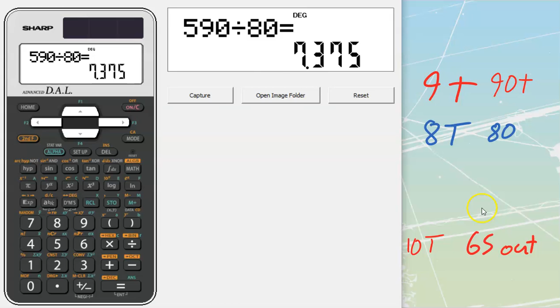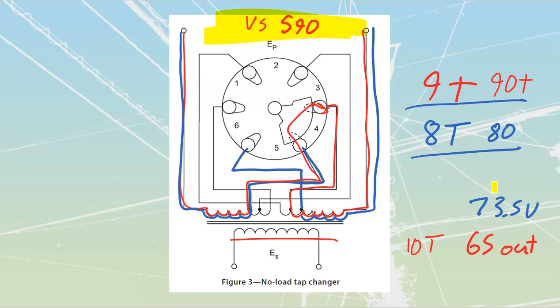So we see that changing the turns does nothing to change this value up top - what we're feeding into the transformer doesn't change. All it's doing is changing the number of volts per turn dumped on the output side. Moving to position number 5, we found a higher voltage out. As we move to position 4, we get a lower output. As we move to position 3, it introduces another turn, so it gets lower, and so on as we go through these.